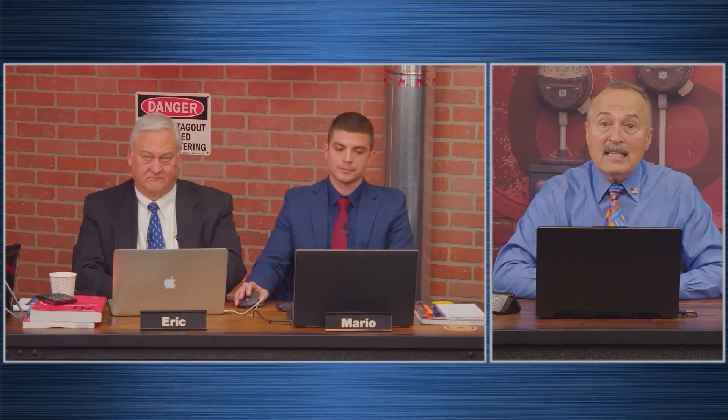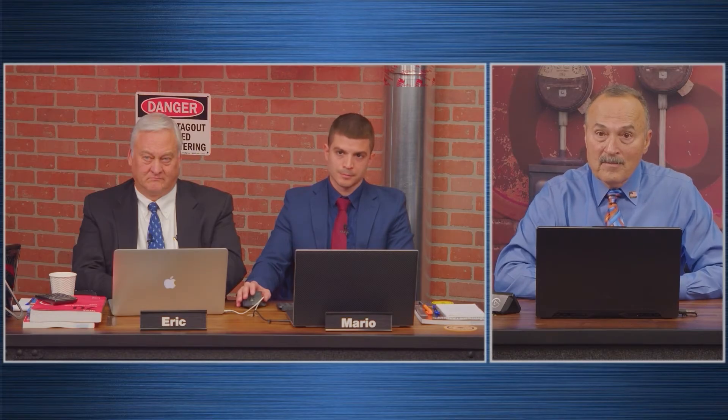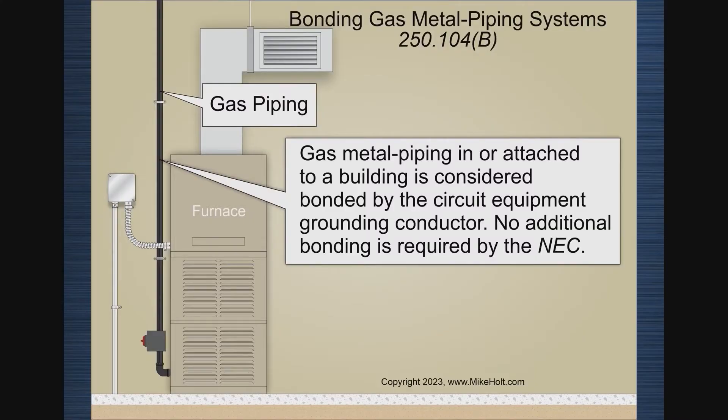Let me phrase it differently: if equipment is being supplied that is likely to become energized and the circuit does not contain an equipment grounding conductor, then it shall be bonded. Looking at a graphic here — metal gas piping in or attached to a building is considered bonded by the circuit equipment grounding conductor. No additional bonding is required by the NEC.